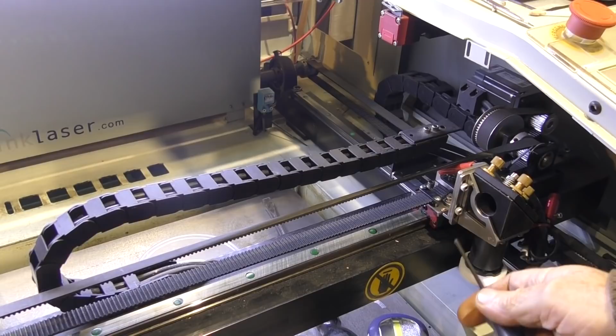I'm catching the beam into the right place by moving and adjusting the head. Your head will have some Y adjustment on it, so you'll have no problem doing that. But what you won't have is any Z adjustment to make it true in that direction. And that's the other secret about this machine. I've got Z adjustment on here, which allows me to move up and down. Now at the moment I don't need this Z adjustment. I've just set X true to this rail here, both in that plane and in this plane. Otherwise the dots would not coincide.